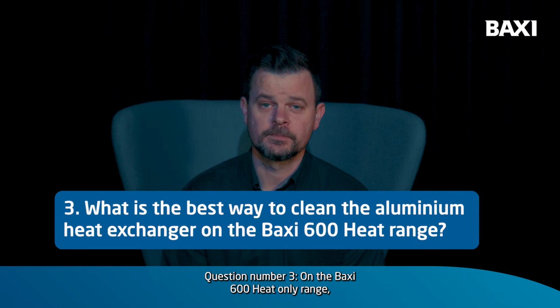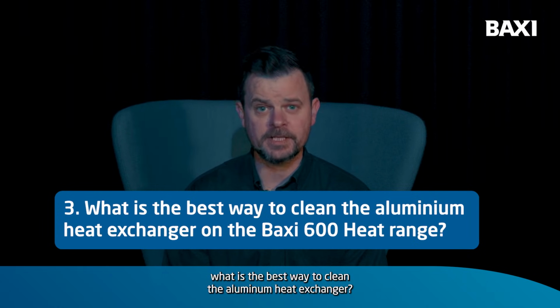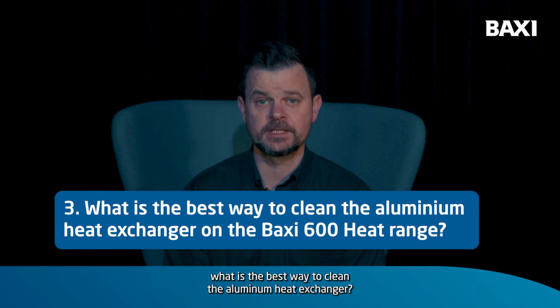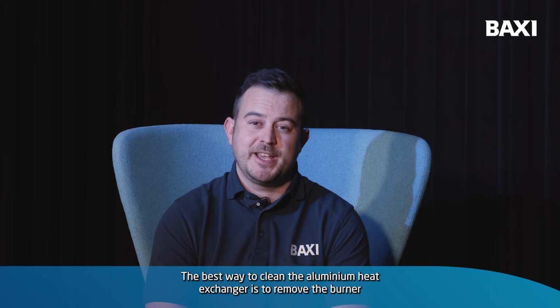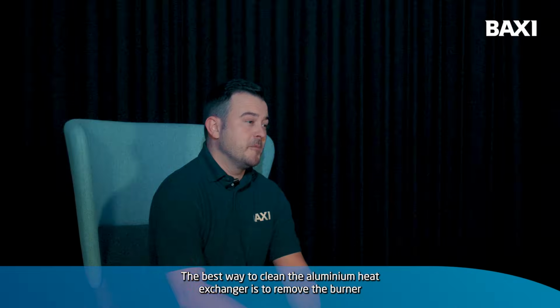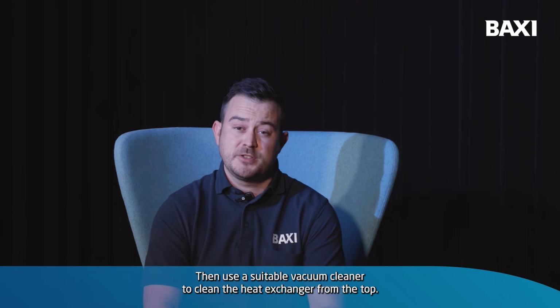Question number 3. On the Baxi 600 heat-only range, what is the best way to clean the aluminium heat exchanger? The best way to clean the alley heat exchanger is to remove the burner and gasket from the top. Then use a suitable vacuum cleaner to clean the heat exchanger from the top.